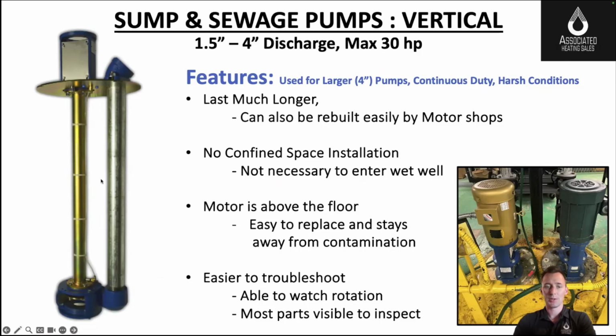I would say they also last quite a bit longer, and motor shops can rebuild them at least once in their lifetime. So a new shaft, new bearings, and the pump is back running, because the motor is usually quite good for a long time. Some advantages there that we just described would be, hey, it's a long-lasting pump and it does really well with those conditions that are a little harsher.